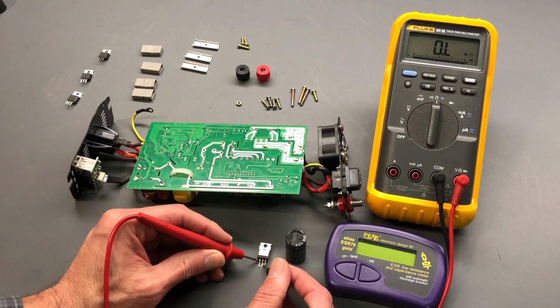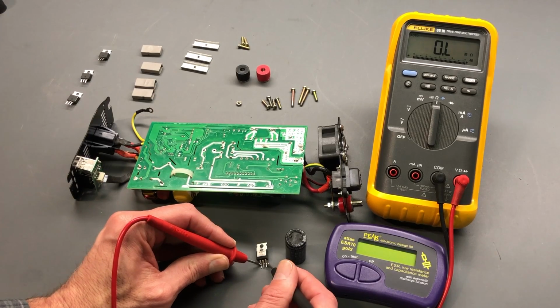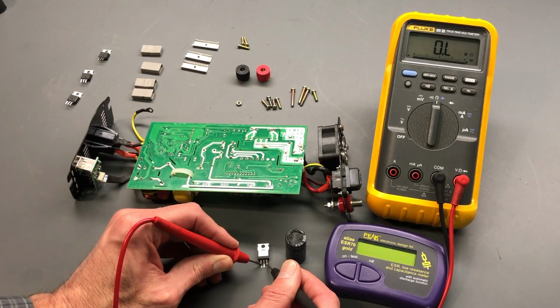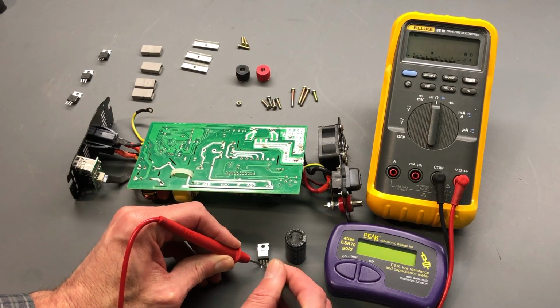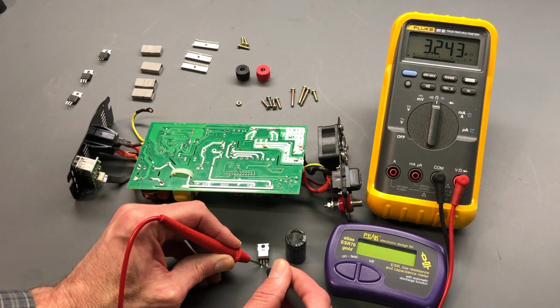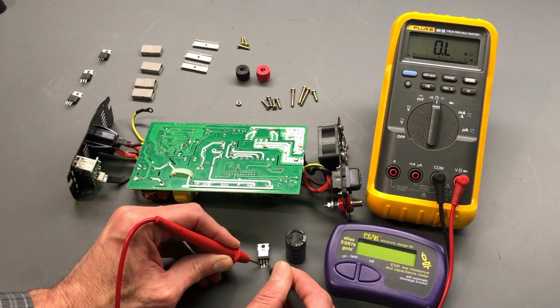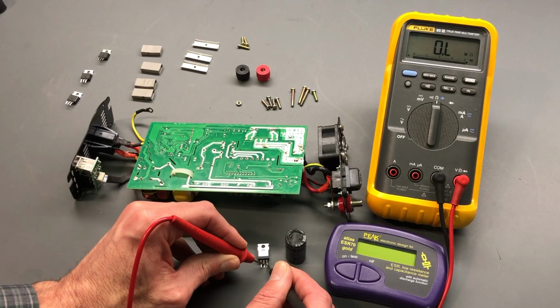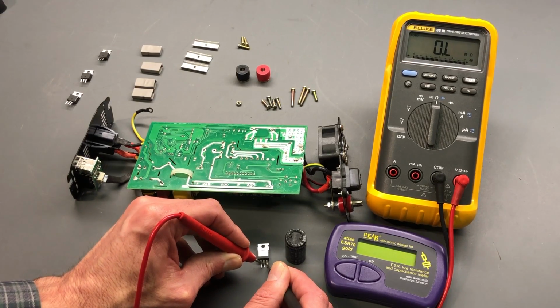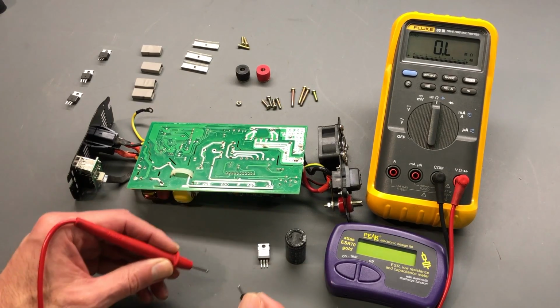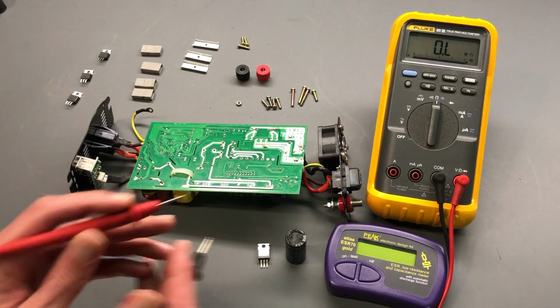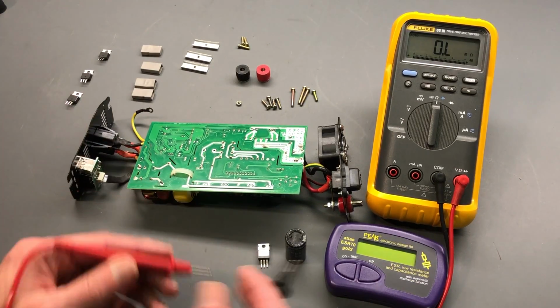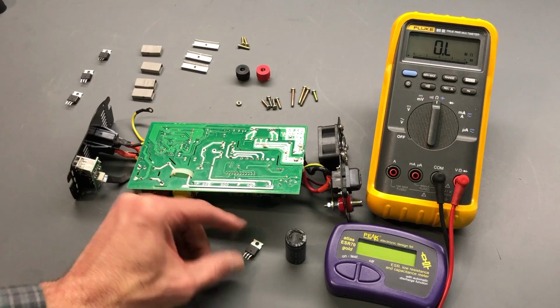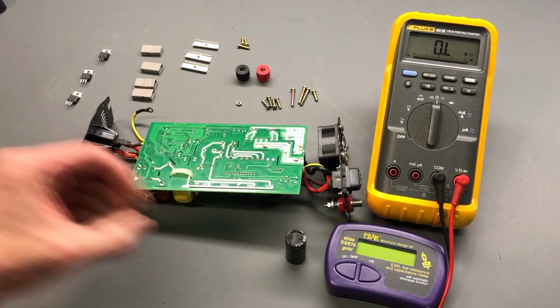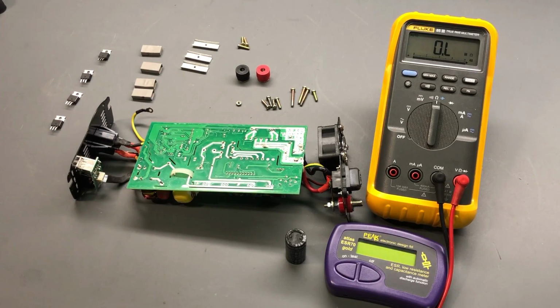Come over here on this one. So this one actually shows 3.2 megohms, but the outer leads show open, middle to the right hand shows open. Either this one failed and is completely burned open inside, or maybe it is actually good, but it tests different than all the others, but clearly will get replaced.